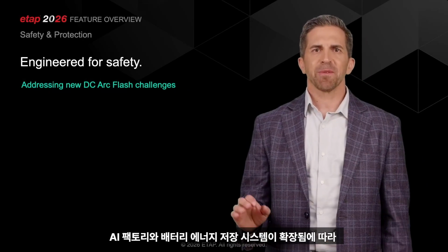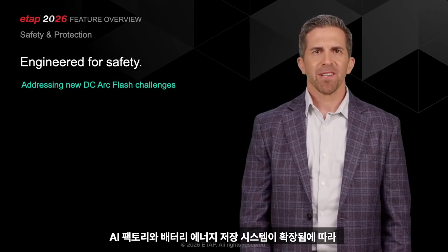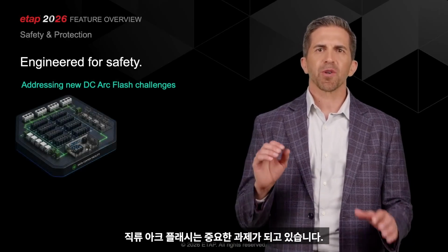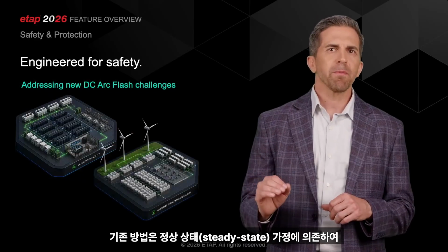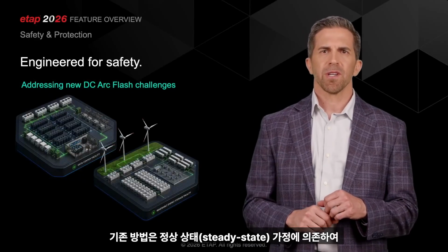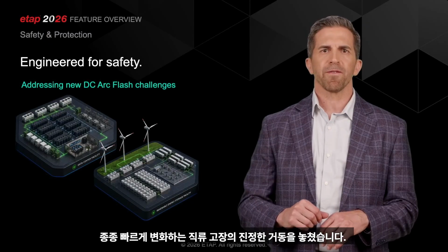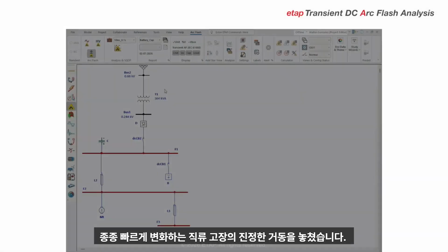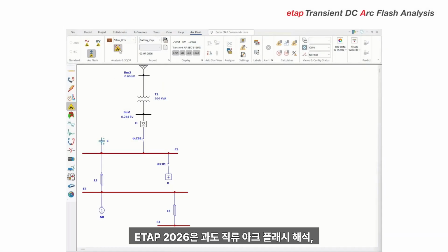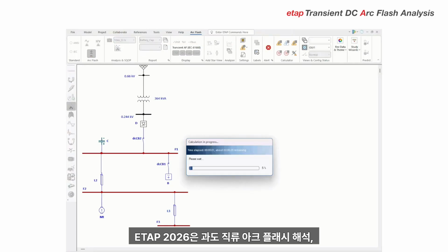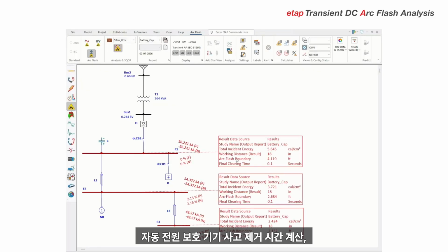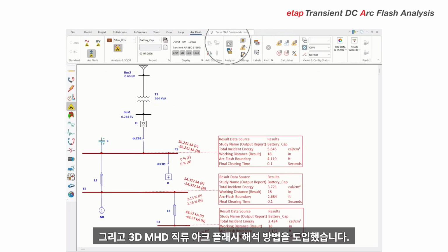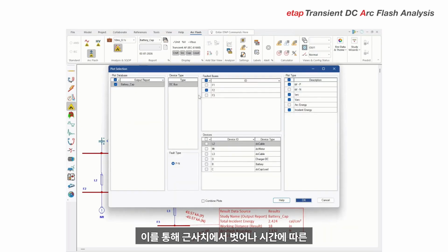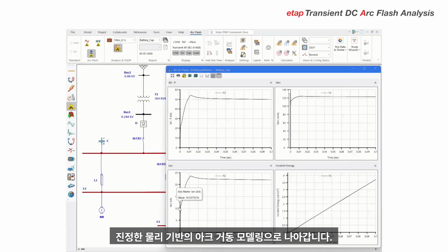As AI factories and battery energy storage systems scale, DC arc flash is becoming a critical challenge. Traditional methods rely on steady-state assumptions, often missing the true behavior of fast-evolving DC faults. ETAP 2026 introduces transient DC arc flash analysis, an automatic source protective device clearing time calculation, and the 3D MHD DC arc flash analysis method. This moves us from an approximation to true physics-based modeling of arc behavior over time.